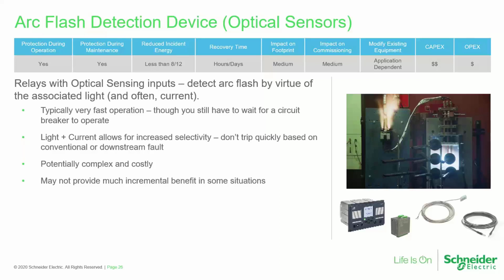Well, the problem is you still have to trip a circuit breaker. And so you've got 3 cycles or more that you wait for that to happen. That's why in one of our application notes, we say it may not provide much incremental benefit in some situations. We need to look not just at the relay, but what does it have to connect up to in order to clear the fault from the system. Impact on commissioning is more, again, some of the things that we've already talked about.